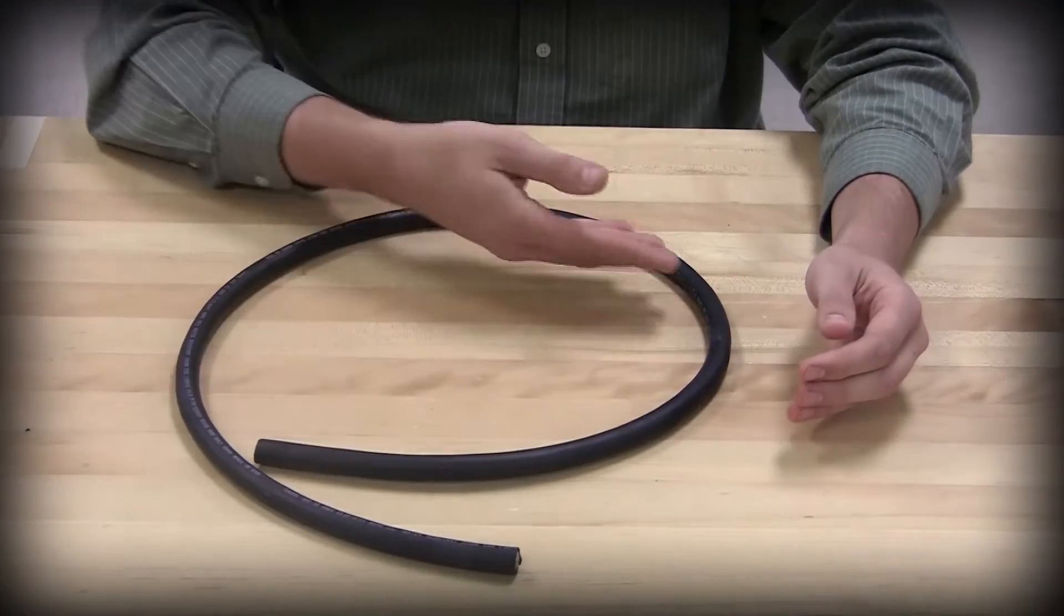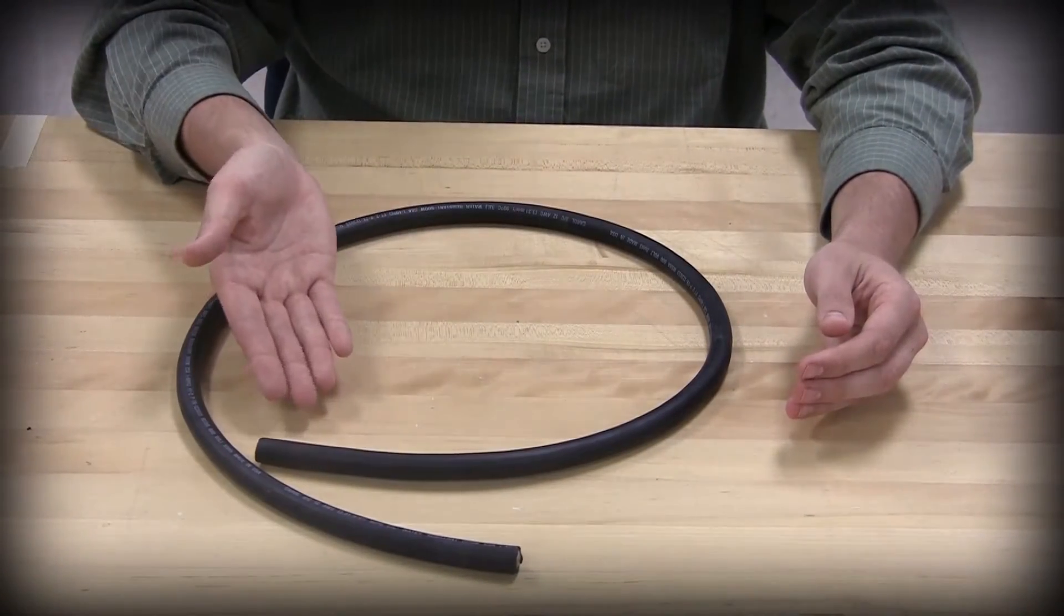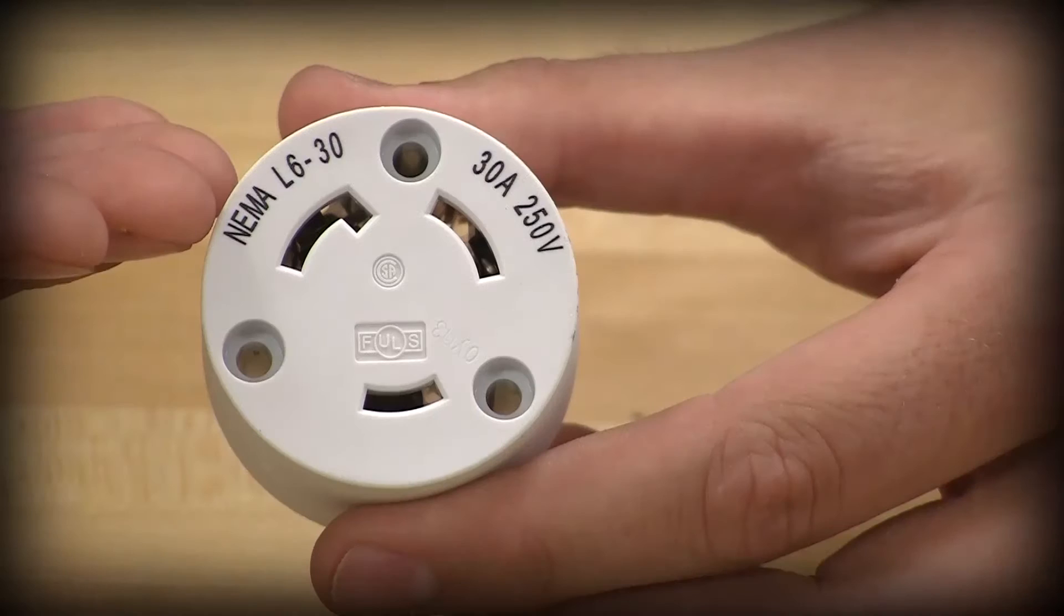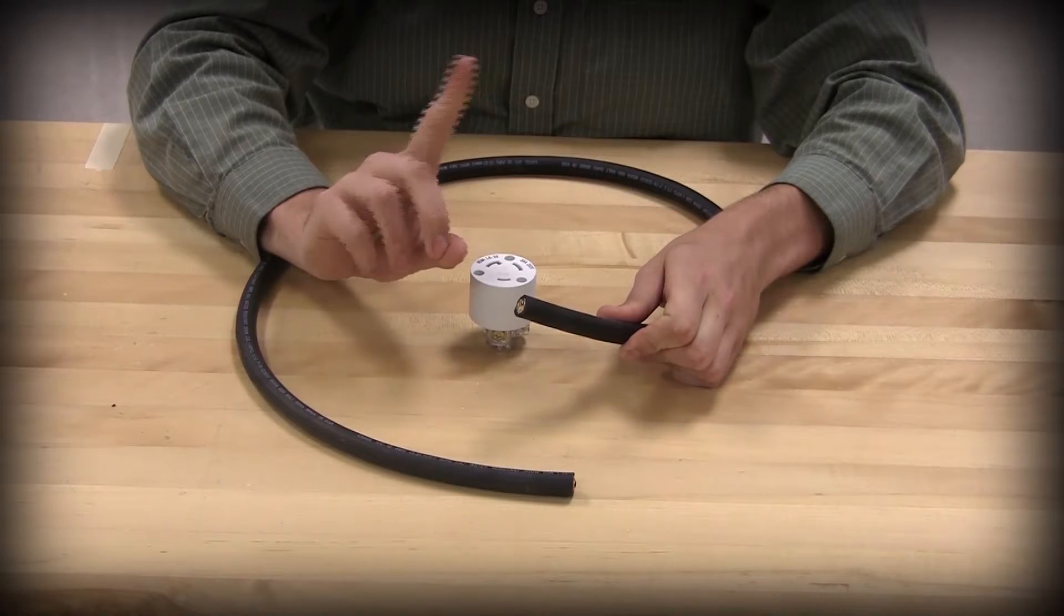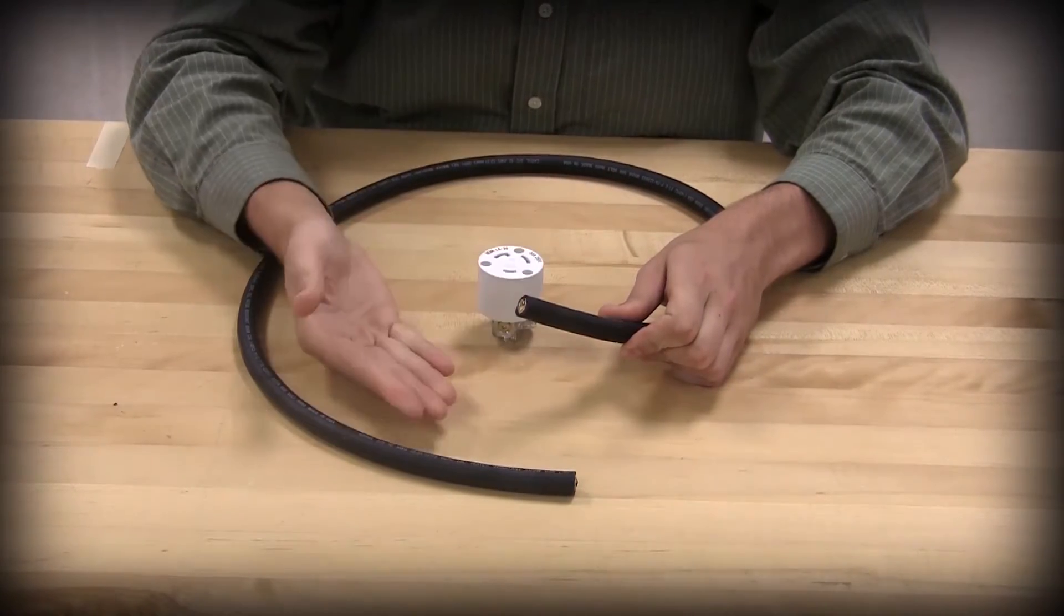For this application we'll be using a 12 gauge wire with a 30 amp 250 volt 3 wire connector. It is important that you do not pre-strip the cord jacket or conductors before assembly.